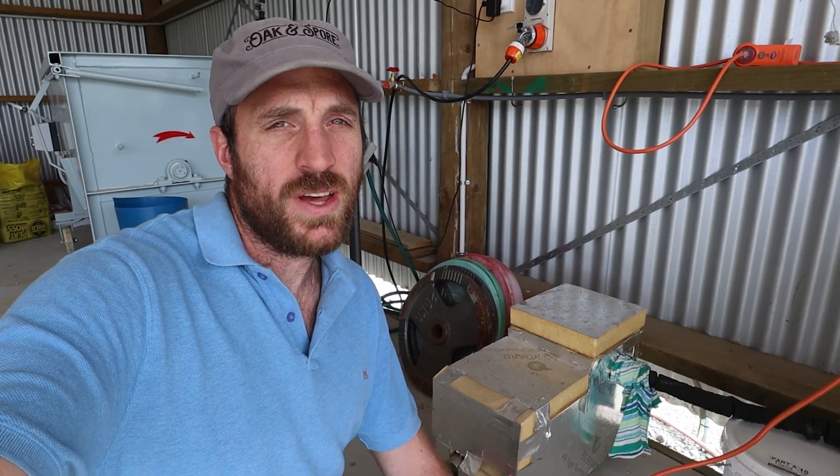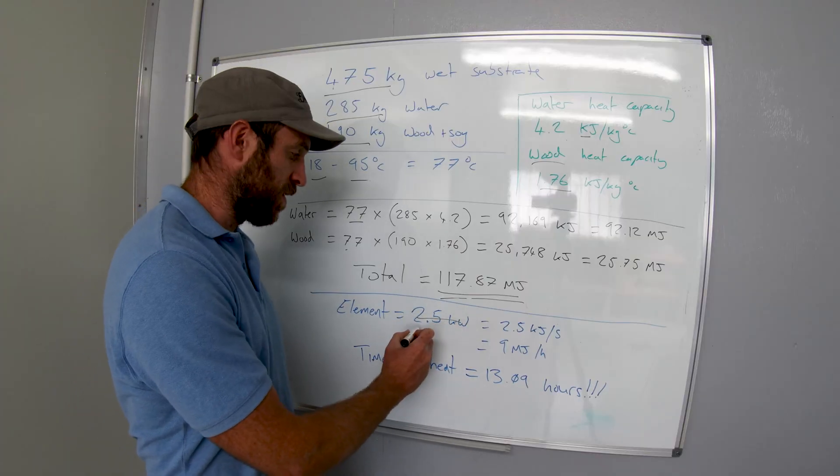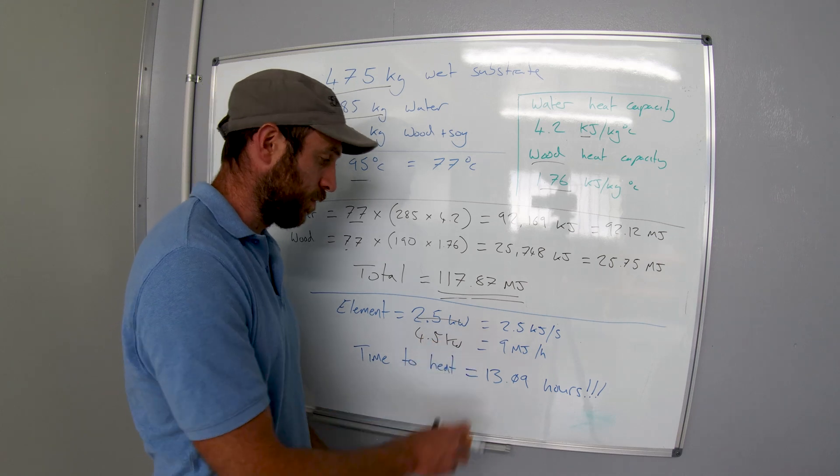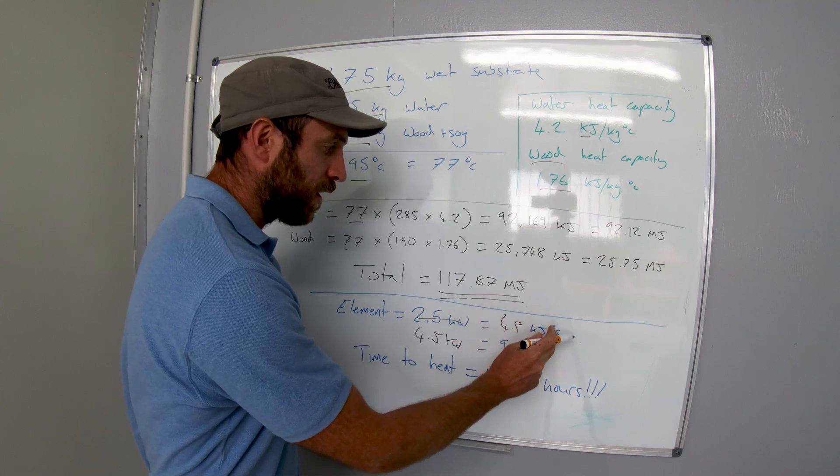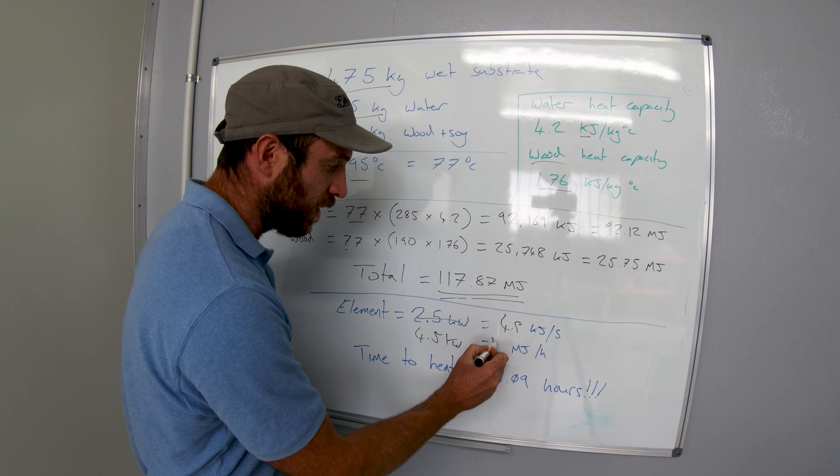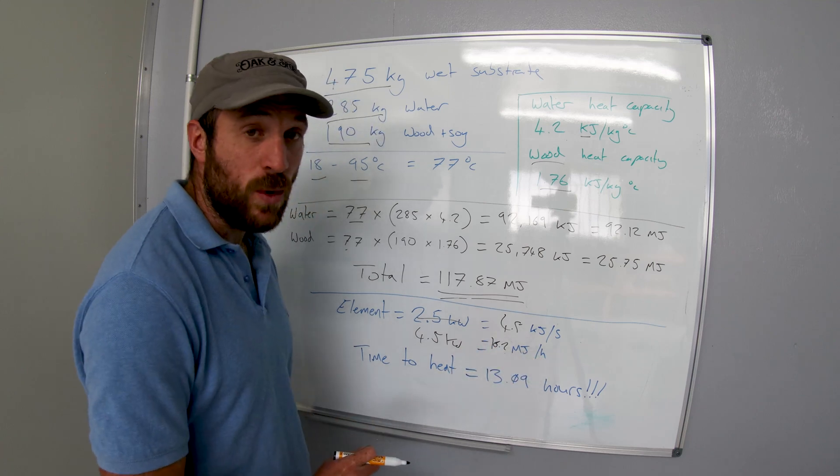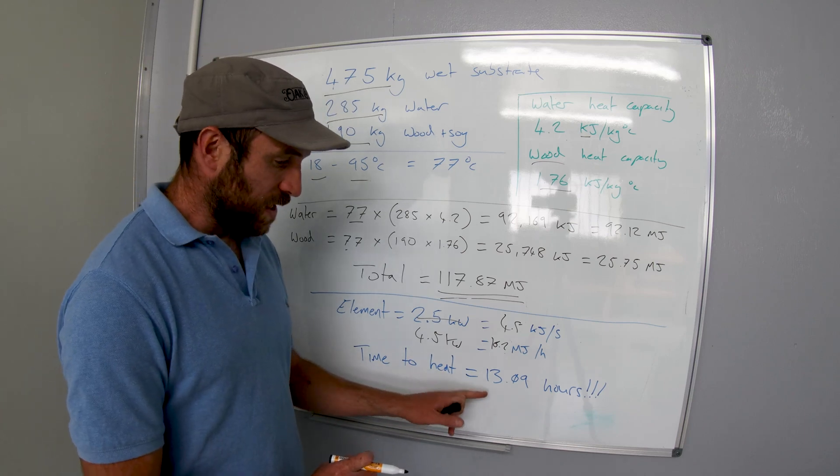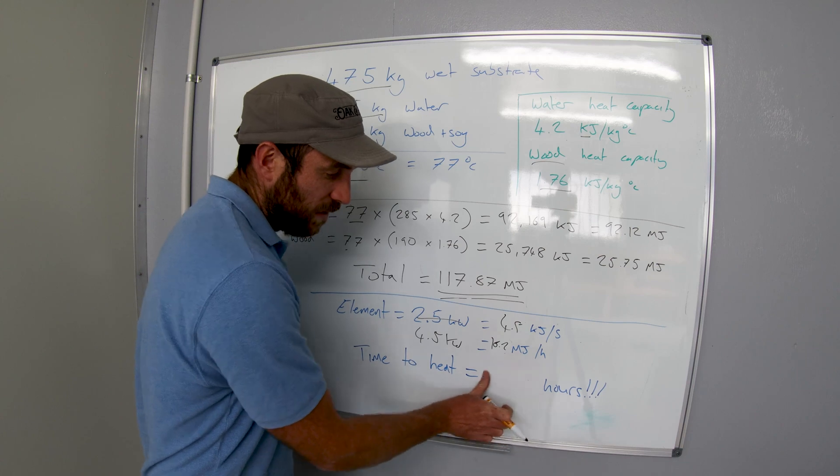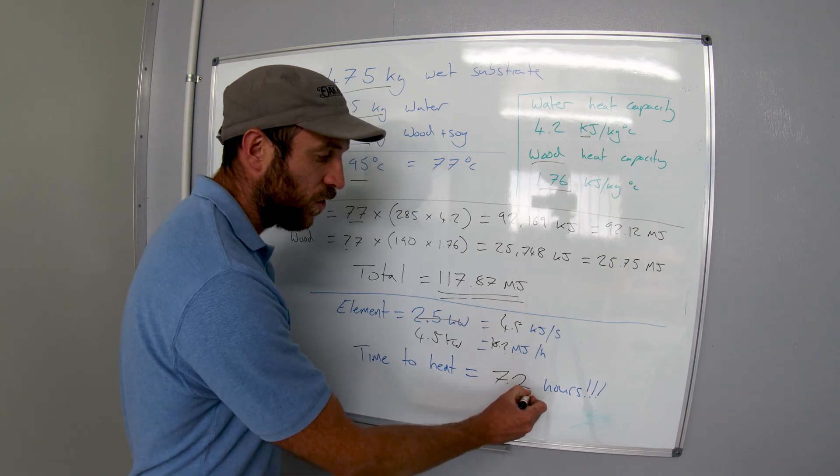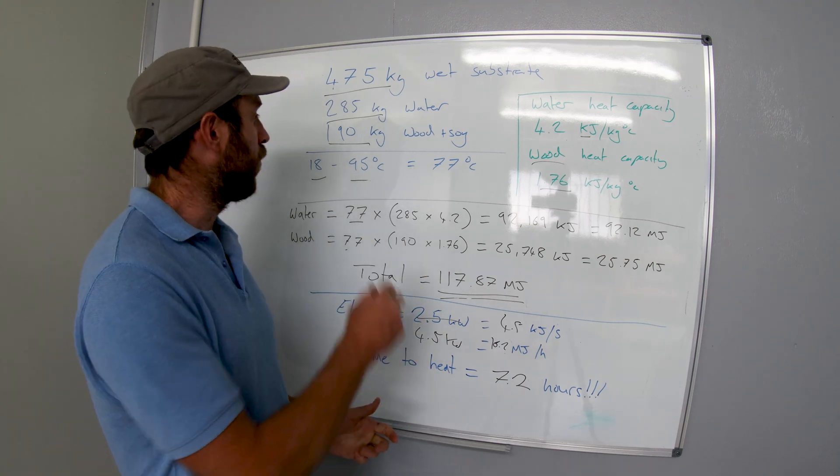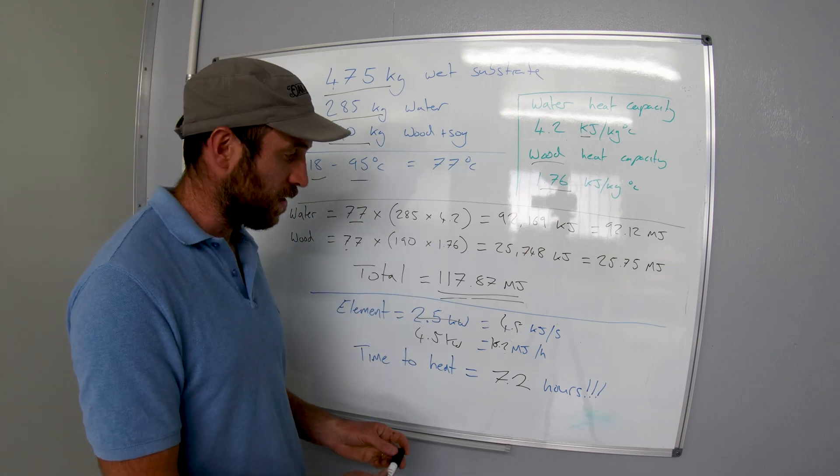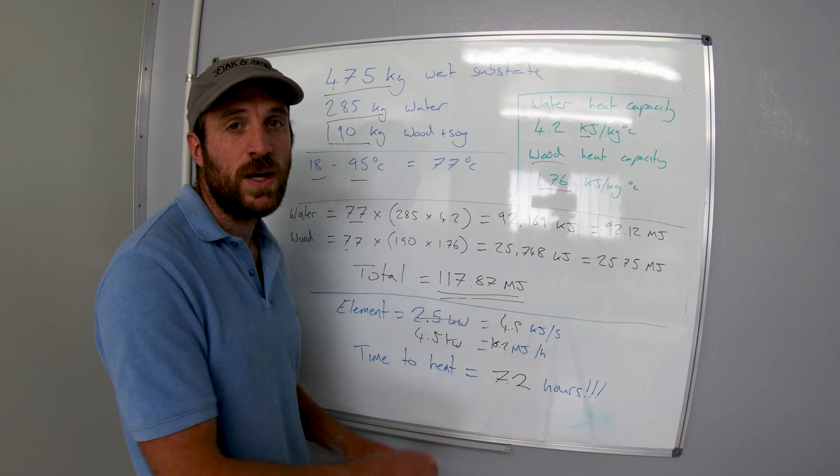But how much time will that take off the heat up? Well we can actually calculate that as well. Instead of a 2.5 kilowatt element we're going to put in a 4.5 kilowatt. 4.5 kilowatt element gives us 4.5 kilojoules a second or 16.2 megajoules an hour. Now that takes the time to heat up from 13.09 hours down to 7.2 hours. That means we can heat up roughly half a ton of substrate from 18 to 95 degrees Celsius in 7.2 hours.